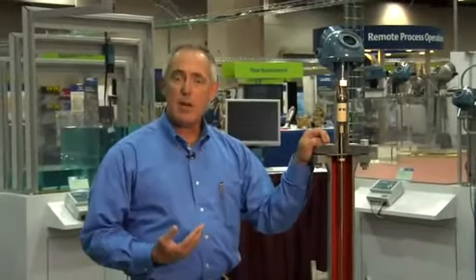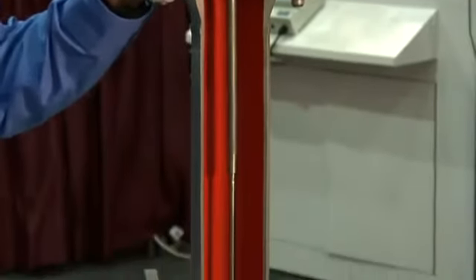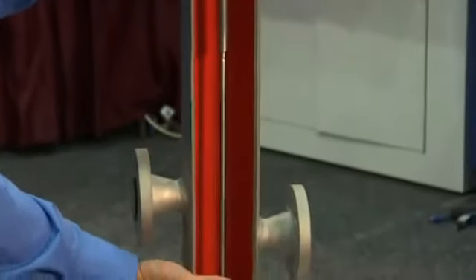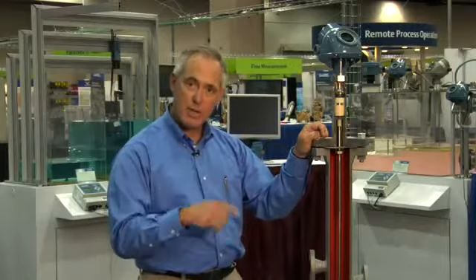Specifically, I'll cover 3 features of this device that really do make it ideal for measuring these types of levels. The first feature that we'll cover is called dynamic vapor compensation. To explain that, I'll refer to this device here. As you may or may not know, a guided wave device measures level by sending a microwave down to the product surface and then looking for the reflected signal back. We time how long it takes that signal to go down and back.